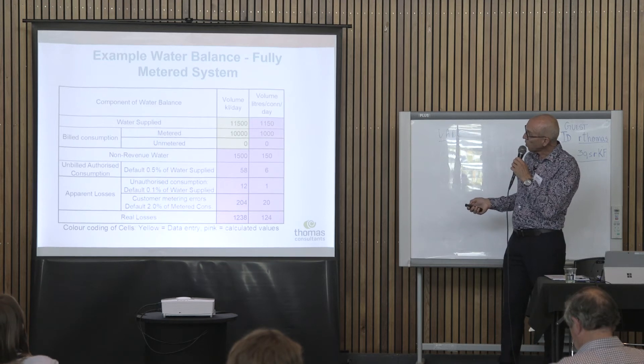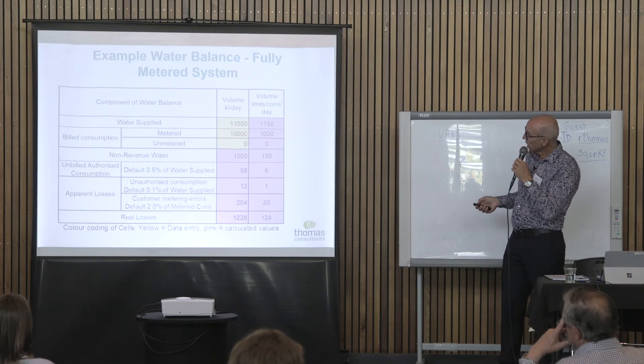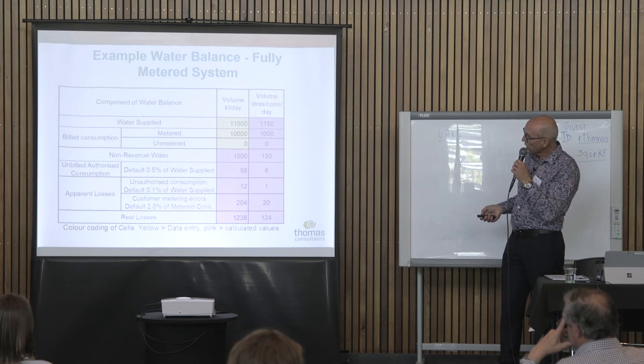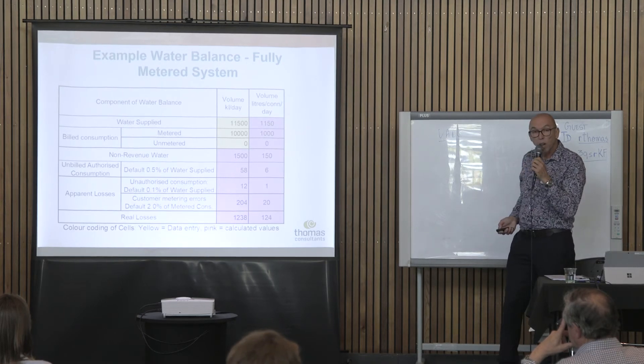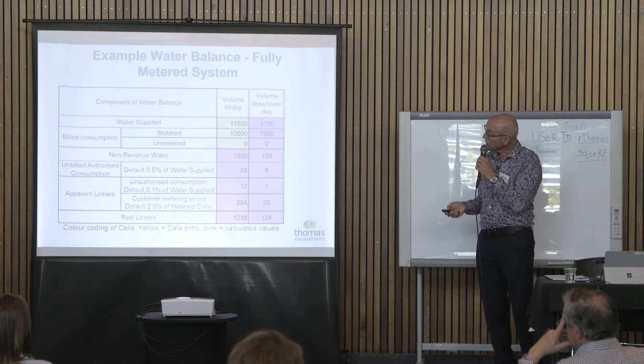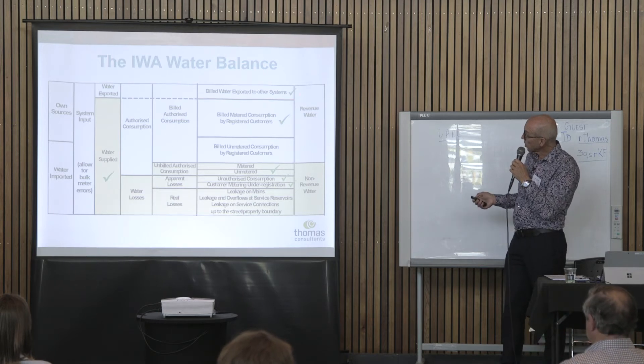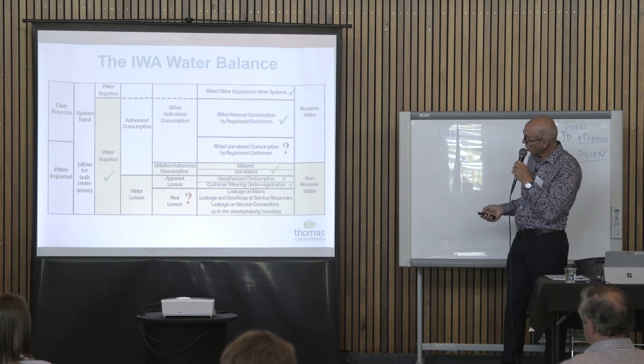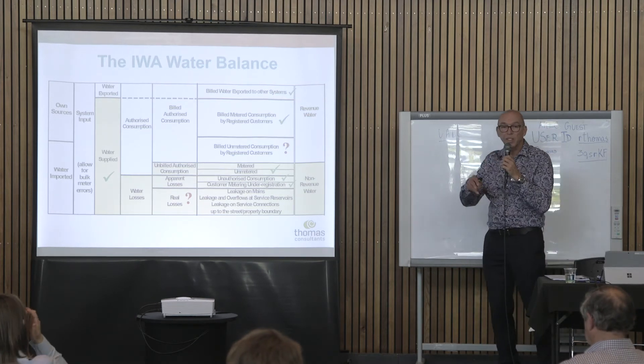Here's an example of a simple water balance: volume of water supplied minus metered consumption gives non-revenue water. Using default values for the minor items, you deduct those and you're left with a volume of real losses for the system. Typically you do this over a 12-month period — it's a volumetric calculation. Some factors you have information on; others you have to assess, and what you assess here determines the level of real losses. That's partly why we have this water loss training seminar.